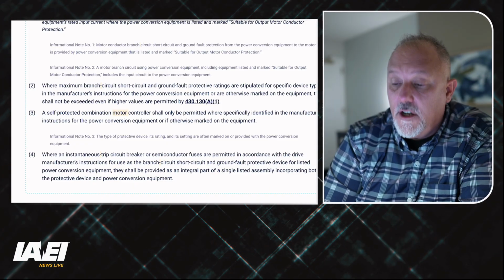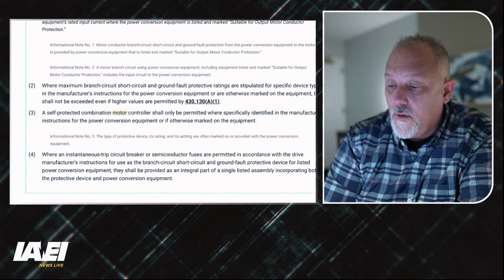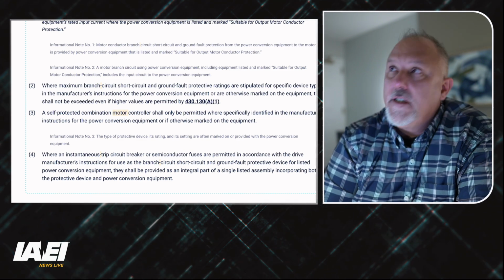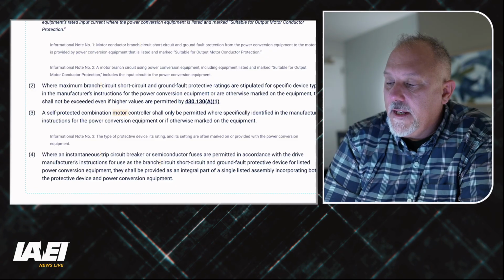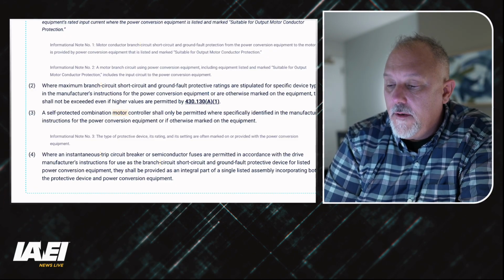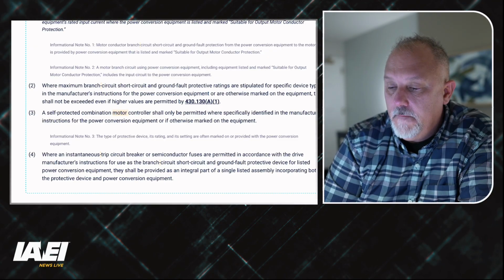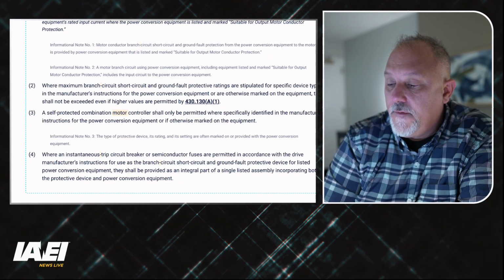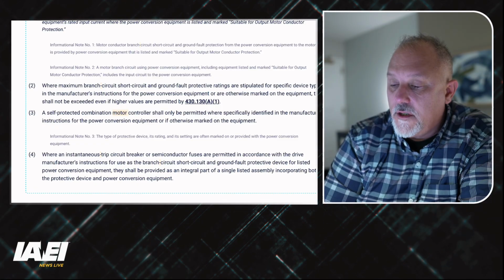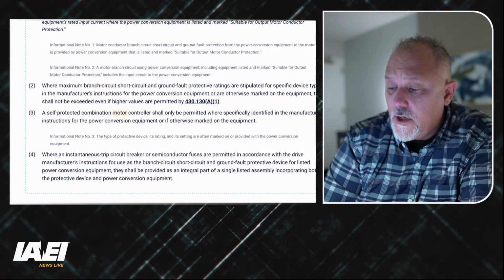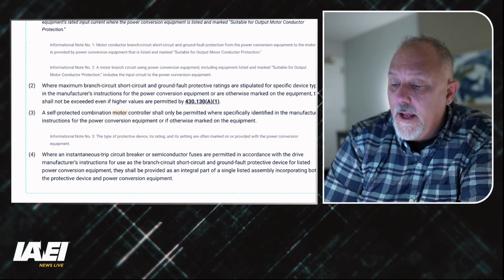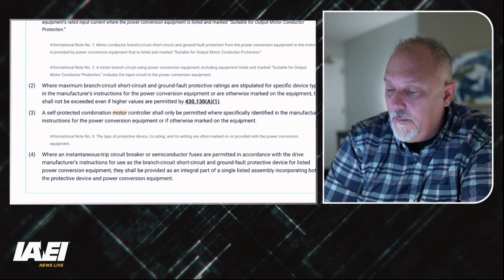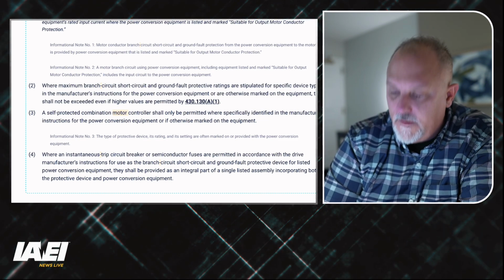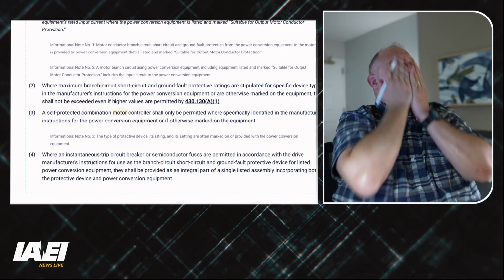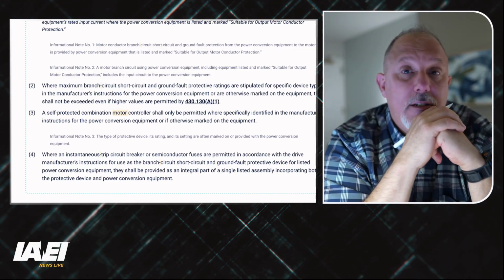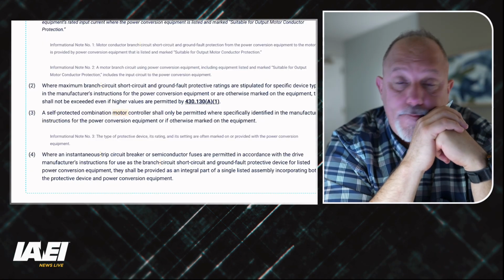And then they talk about a self-protected combination motor controller. Self-protected motor controller, where specifically identified in the manufacturer's instructions for the power conversion equipment, or if otherwise marked on the equipment, where an instantaneous trip circuit breaker or semiconductor fuses are permitted in accordance with the drive manufacturer's instructions for use as the branch circuit, short circuit, and ground fault protective device for listed power conversion equipment, they shall be provided as an integral part of a single listed assembly incorporating both the protective device and power conversion equipment. This is not protecting the branch circuit that's supplying. I'm sorry.